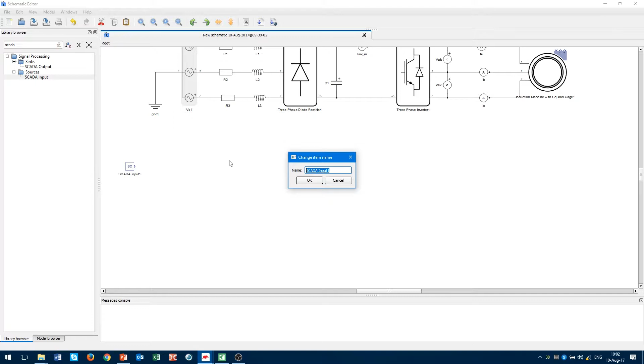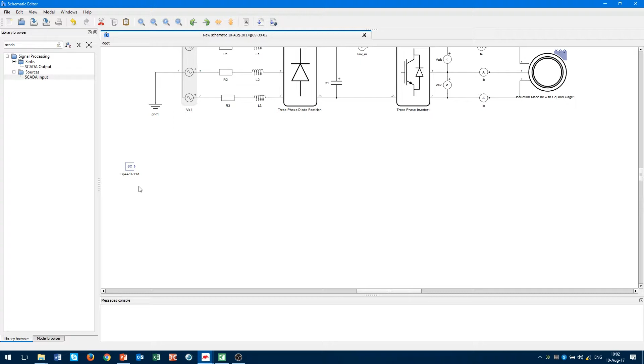We will use this input as a reference for speed. Let's change the label to speed RPM. With a double click in the property window, we will keep signal type as real. The minimum value for the speed will be set to 200, to avoid VF control at very low frequencies, because the machine cannot work with such low frequencies. The maximum value is 1700. The unit will be RPM, revolutions per minute, and the execution rate is TS.